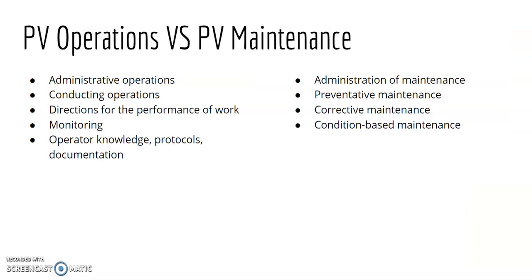For best practice, further monitoring and maintenance on the system needs to be conducted beyond commissioning. These can be broken down into 2 categories, PV operations and PV maintenance. PV operations include 5 areas: administrative operations, conducting operations, directions for the performance of work, monitoring, and operator knowledge, protocols, documentation. Administrative operations means having documentation of the system, including but not limited to plan drawings, inventories, owner and operating manuals, and warranties. Having these on hand and accessible is key when an issue arises and the information is readily available to work towards the solution.